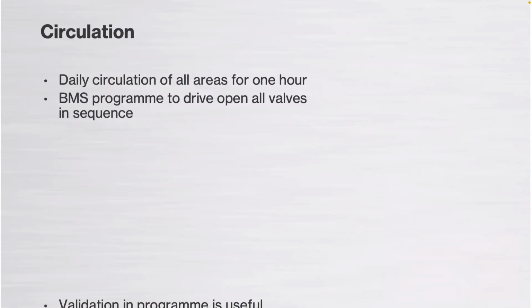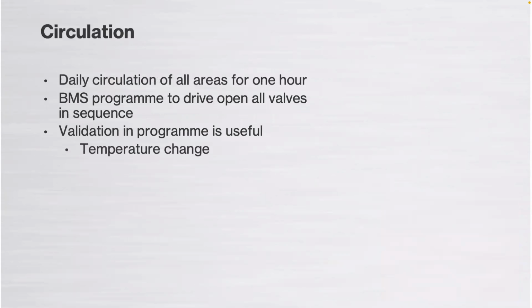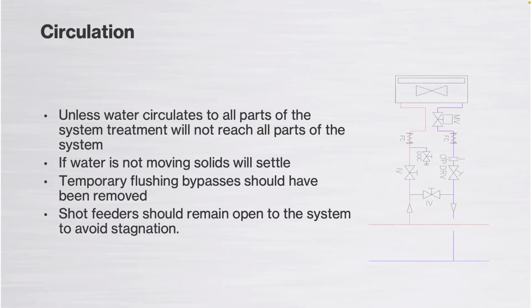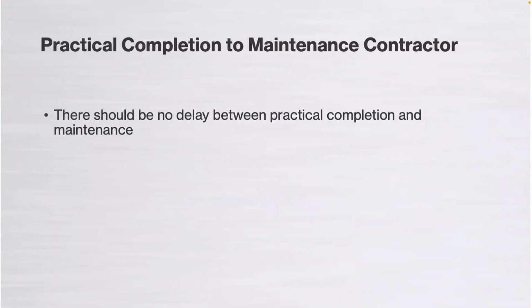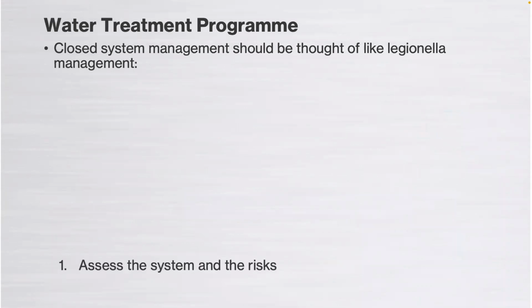First fill and pressure test, think about treatment, essentially all the way through the program. And just to recap again, daily circulation, think about the BMS controls. Temporary flushing bypasses should have been removed. So this image here, the schematic, shows a flushing bypass at a fan coil unit. We'd recommend a line size flushing bypass, for example. Once all the initial velocity has been put through the system and the system's all cleaned, that would be closed, and then you would open up to the unit.